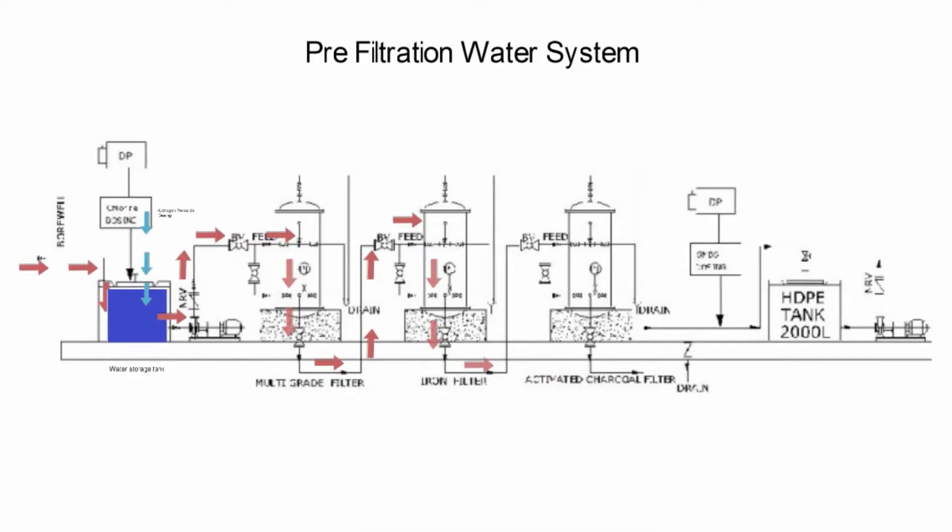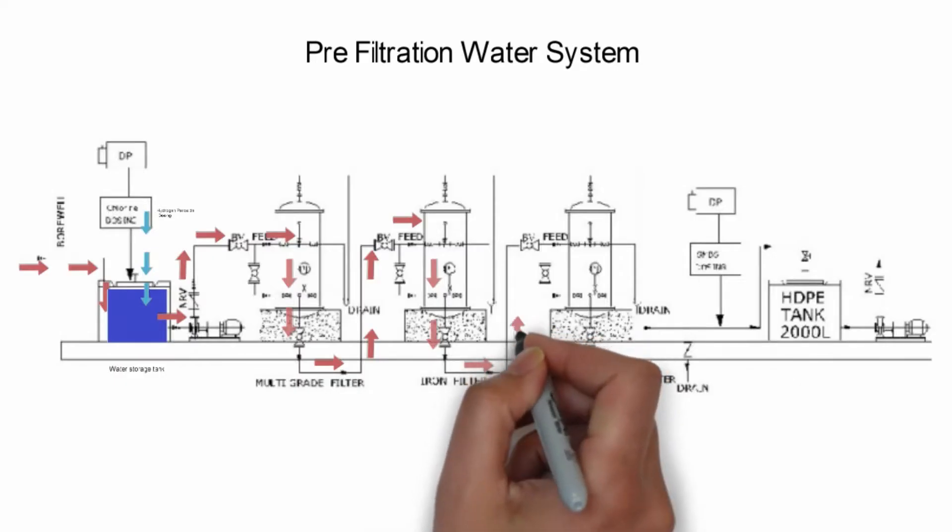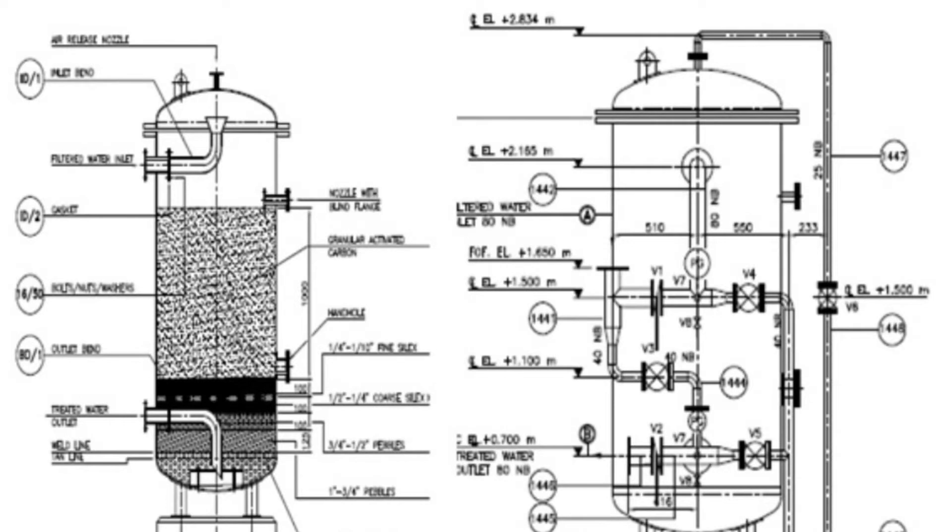Water from the iron removing filter is passed through activated carbon filter, also called ACF. ACF works on the principle of adsorption. The activated carbon filter medium adsorbs the polluted molecules. It is primarily used to remove the color and odor of the water.